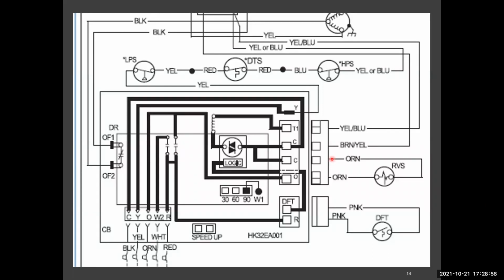So now we can take some of the hot 70, 72 degree air temperatures in the refrigerant, have that send out to the coil and thaw out. At the same time, we're going to close the other set of contacts, come back, go through our W2 terminal. That's going to go into our fan coil or to our furnace and bring on supplemental heat. So now we have a sequence of operation that we understand.